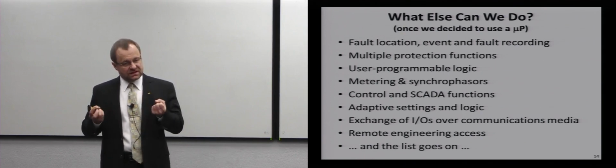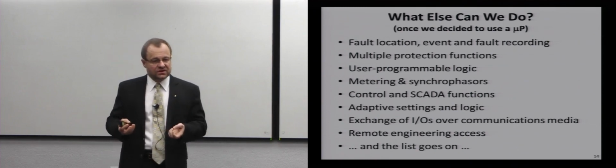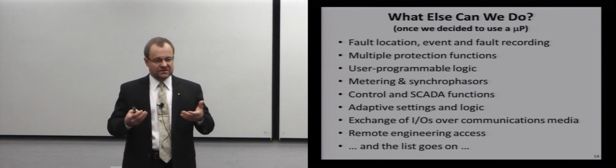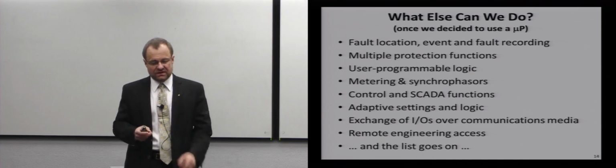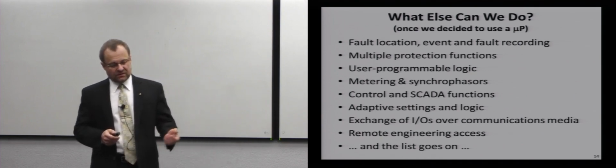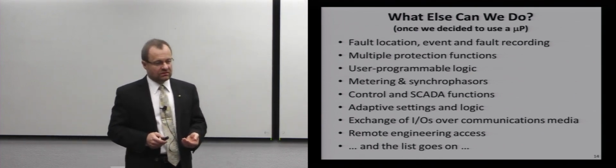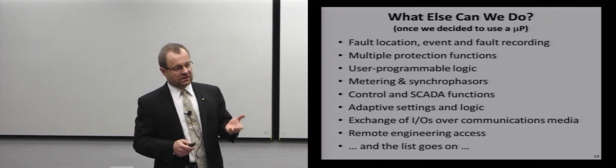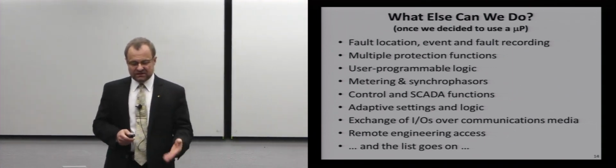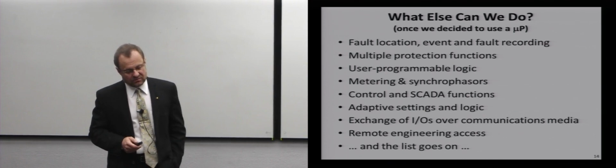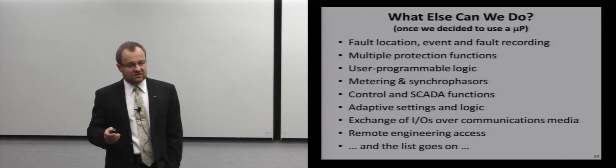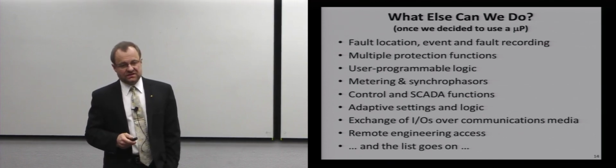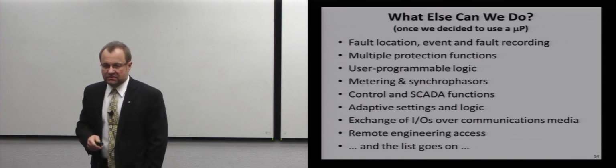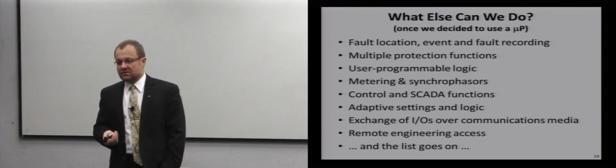We could build a scheme through programmable logic rather than DC wires between the contacts of discrete relays. We could do metering. We could do SCADA control. We could talk with a substation computer and execute commands and provide metering to the SCADA computer. We could change settings on the fly. We could adapt the settings based on the external conditions or on a clock.